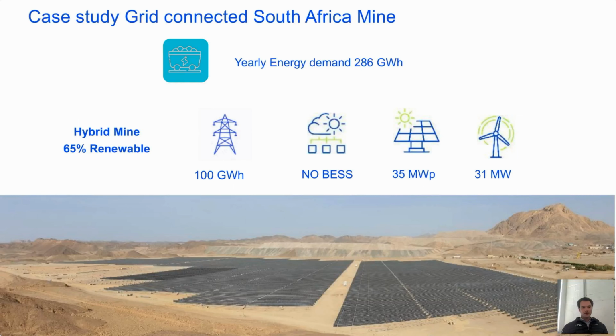So what we provide as a solution is a combination of 35 megawatts solar and 31 megawatts wind. This is sized to avoid or minimize curtailment of power, because their actual maximum demand is about 31 megawatts or MVA 24/7. Without any battery, that gives them about 65% renewable energy penetration.